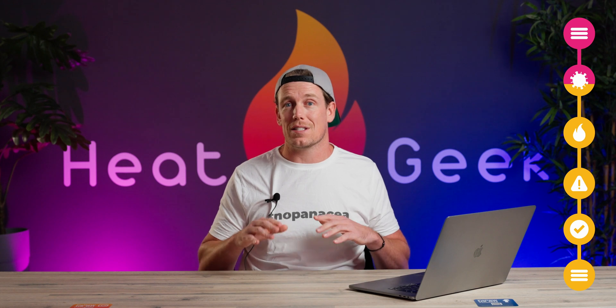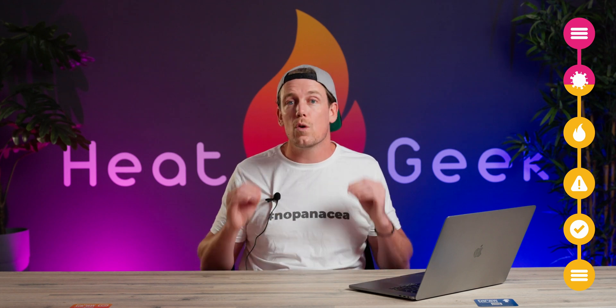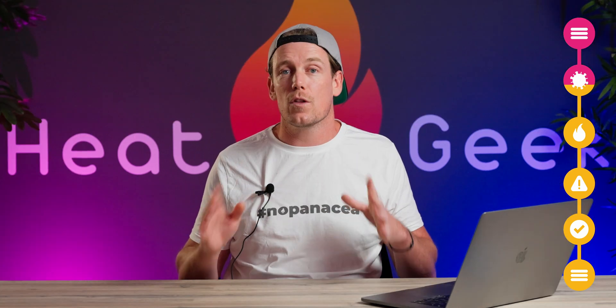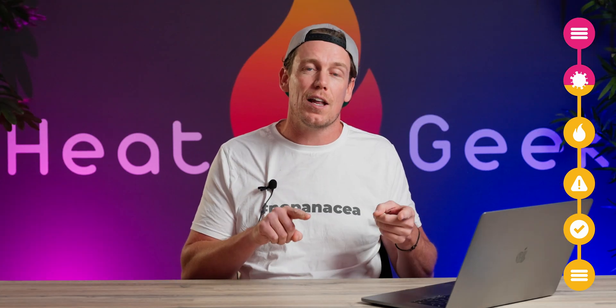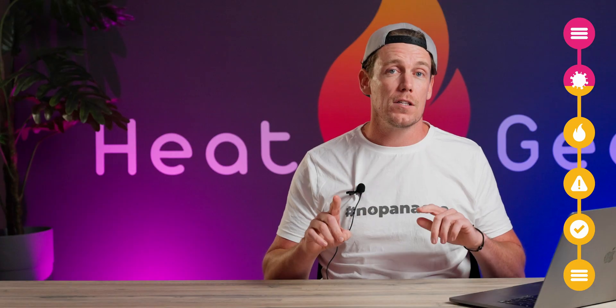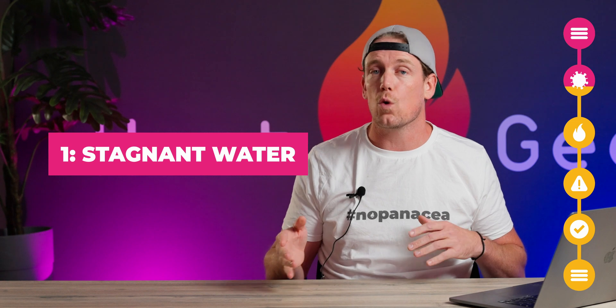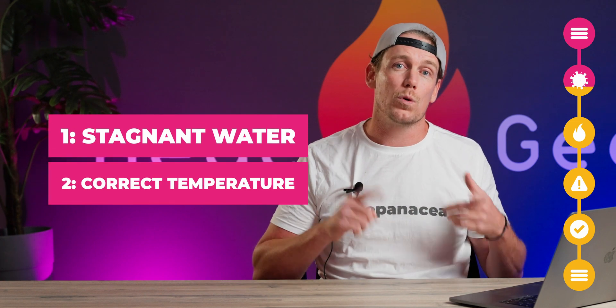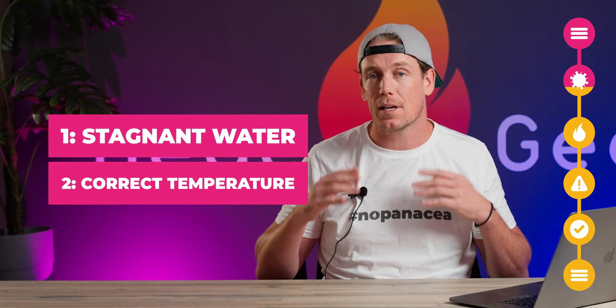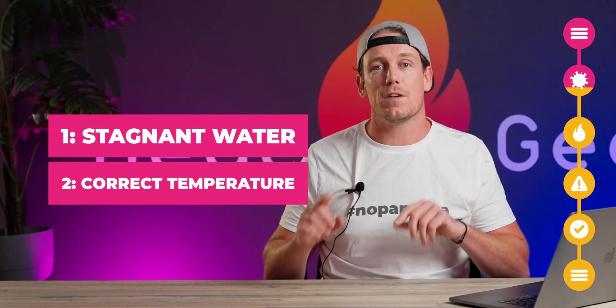The real risk of Legionnaires disease only comes when Legionella bacteria grows to dangerous levels. So the question isn't how do we prevent Legionella — it's how do we prevent Legionella bacteria growth. To grow Legionella to dangerous levels you need two things: first, stagnant water, meaning the water is not moving or changing; and secondly, for that water to be in the Legionella multiplication and growth temperature range of 20 to 45 degrees Celsius.